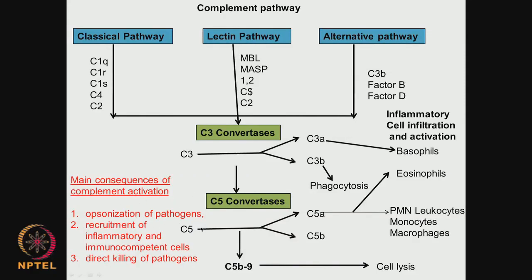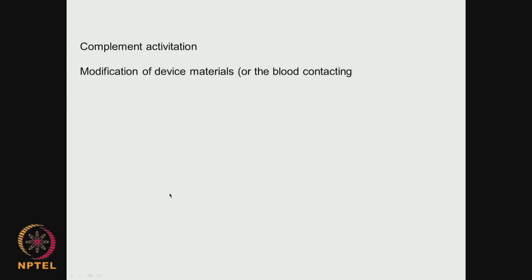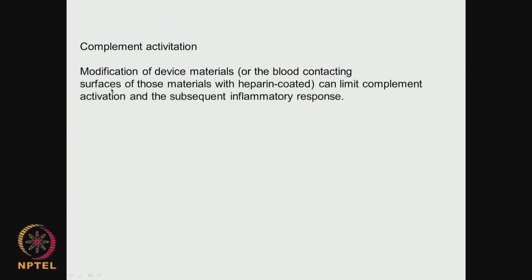The complement system is very fascinating — it identifies pathogens, brings inflammatory and immunocompetent cells, and directly kills pathogens. To prevent complement activation, one approach is modification of device or blood-contacting materials. People have looked at heparin coating — by coating with heparin, it will prevent both complement activation and reduce coagulation, limiting complement activation and subsequent inflammatory response.